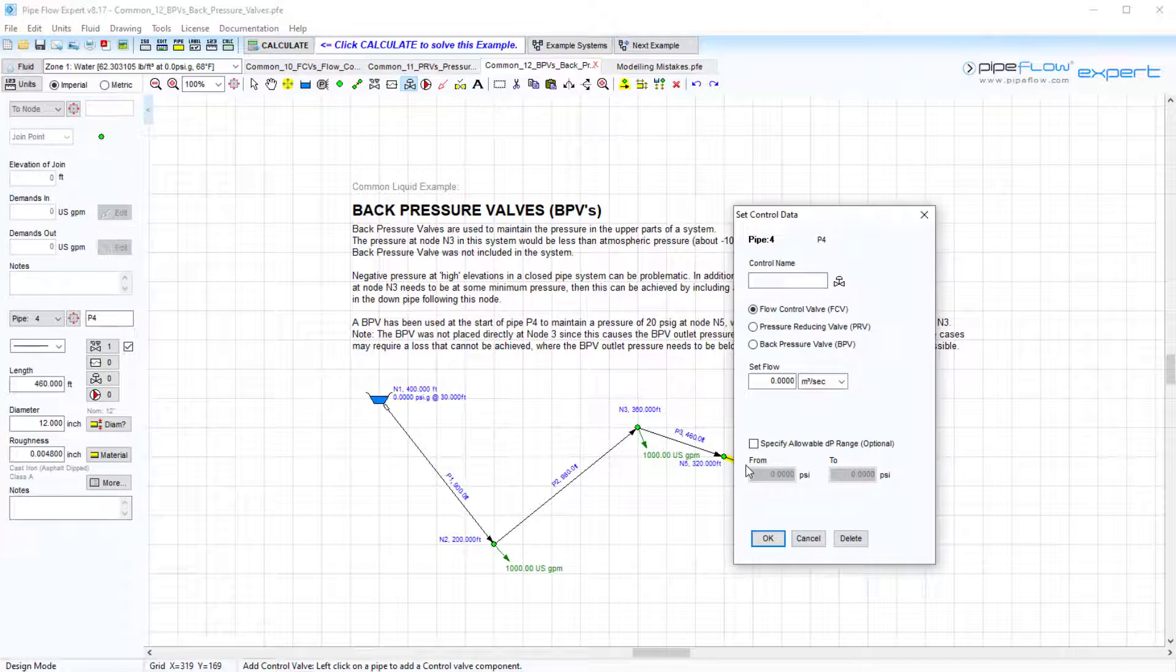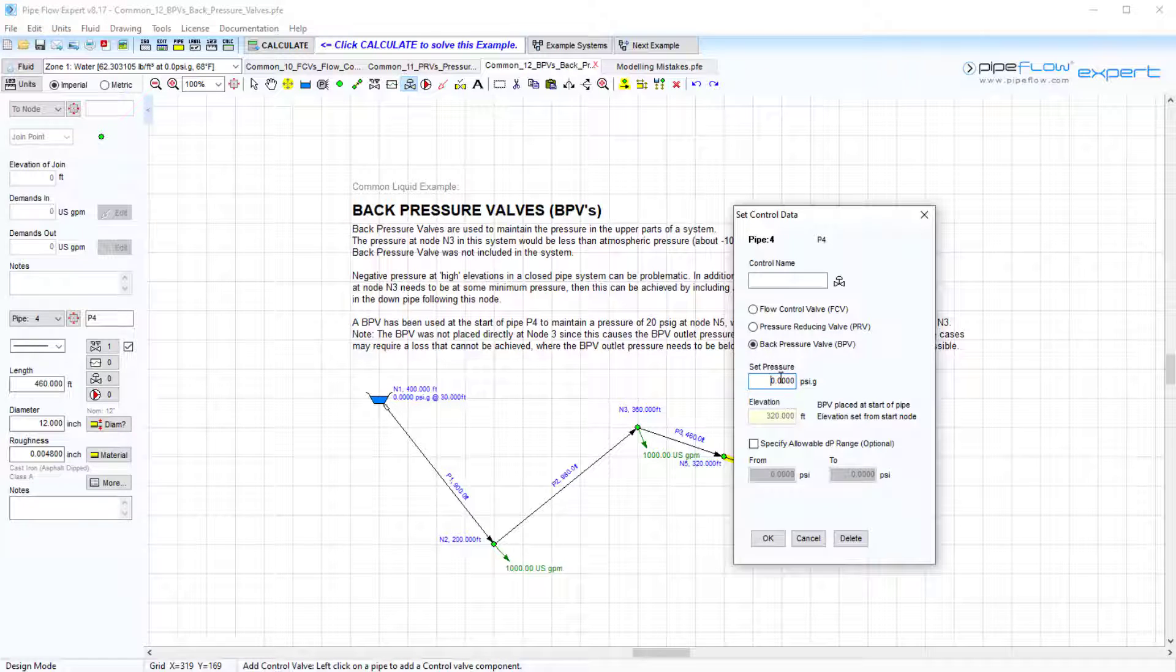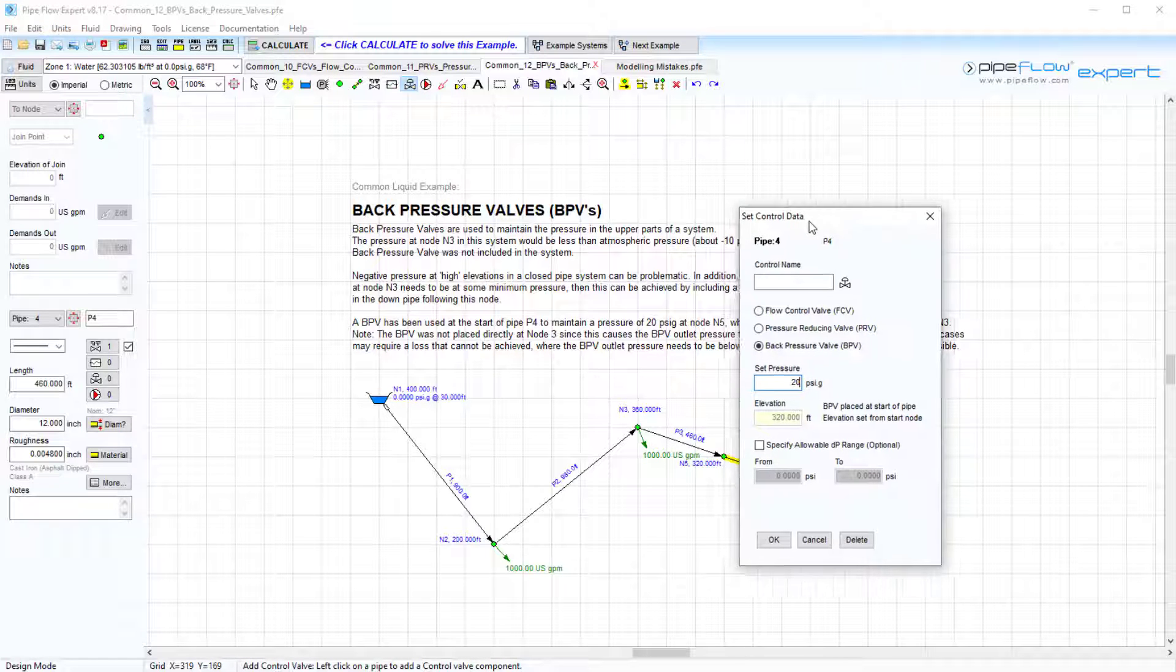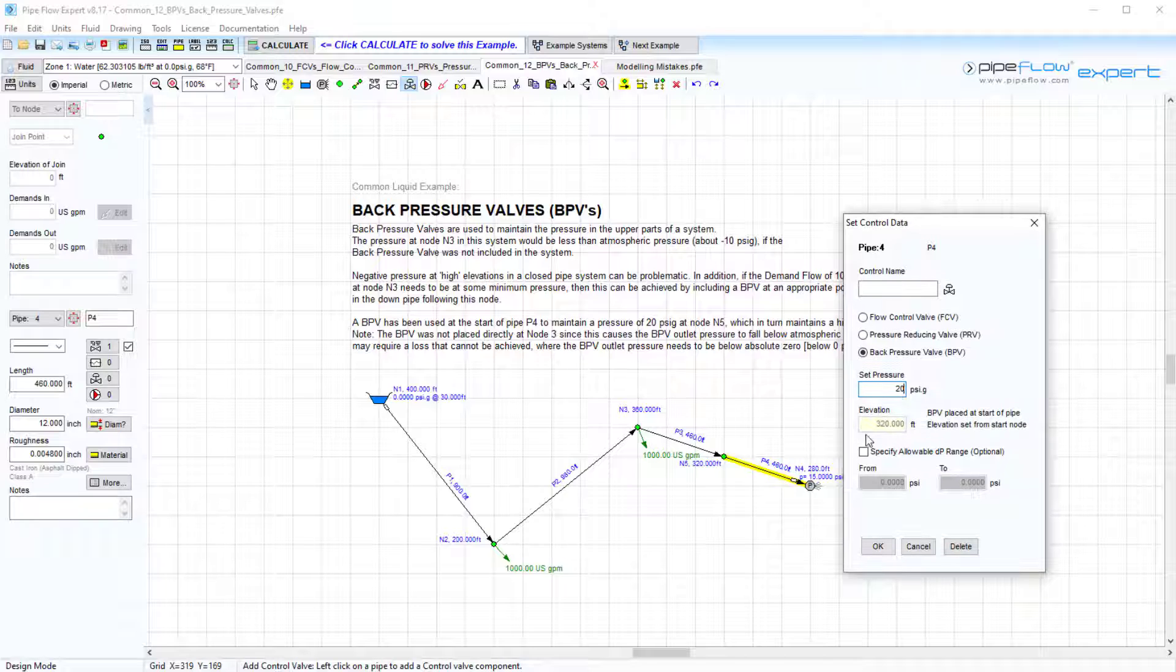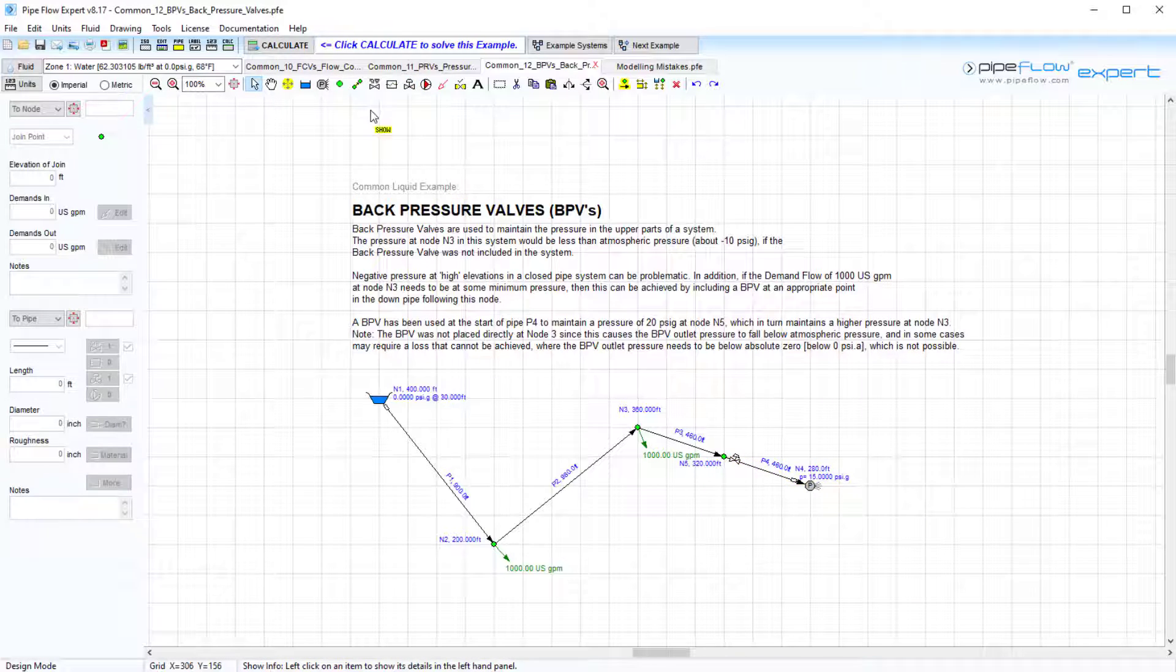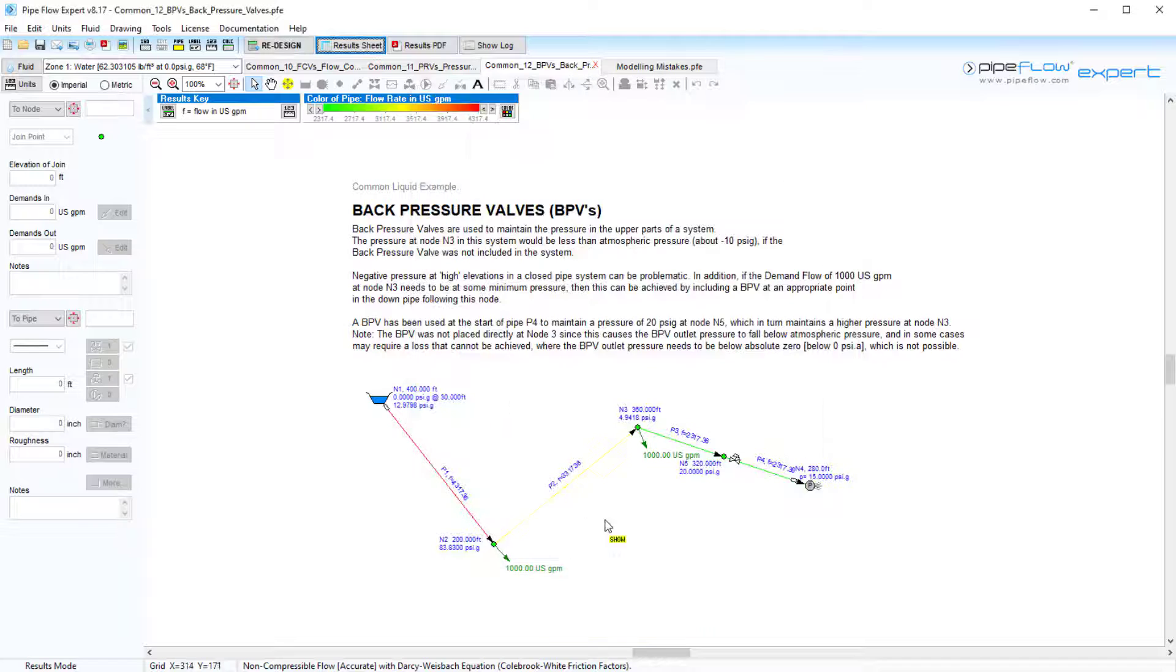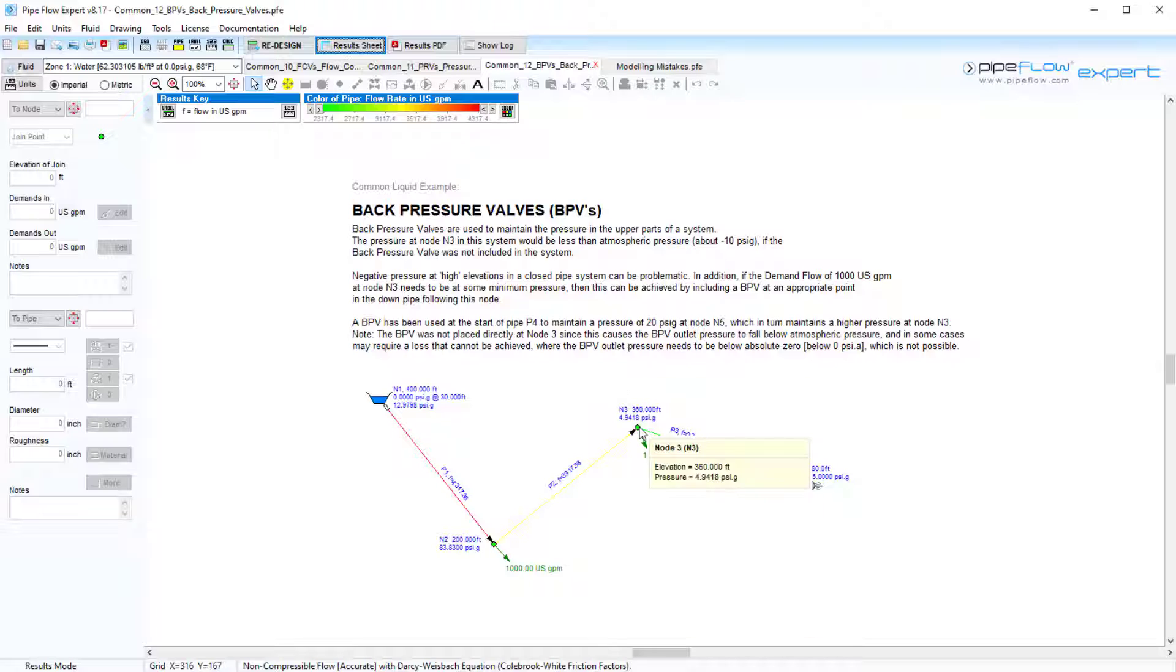We will include a back pressure valve on pipe 4 and enter a pressure value of 20 psi gauge. Again, the elevation is set to the same elevation as the node at the start of the pipe. Let's solve this example now with the BPV. Introducing the valve, we can see that the pressure at node 5 has been maintained at the 20 psi gauge, which in turn maintains a higher pressure at node 3.